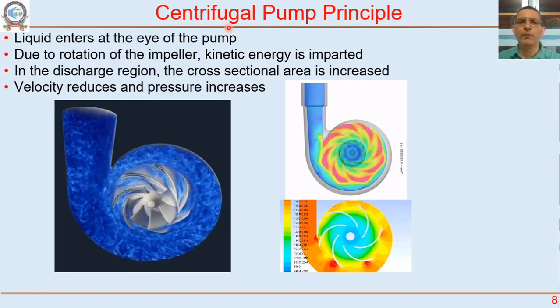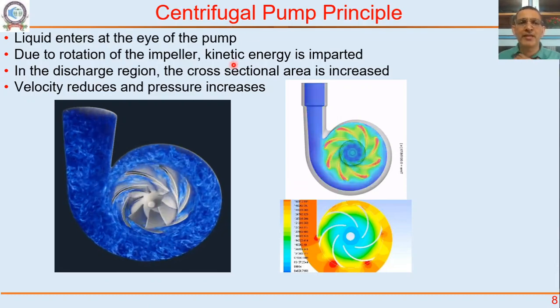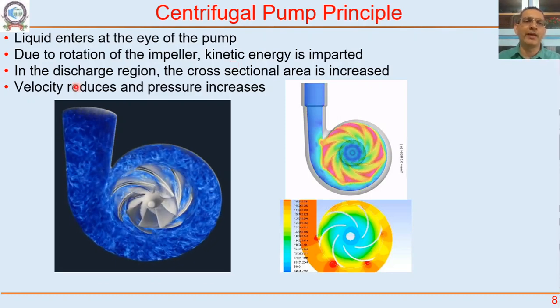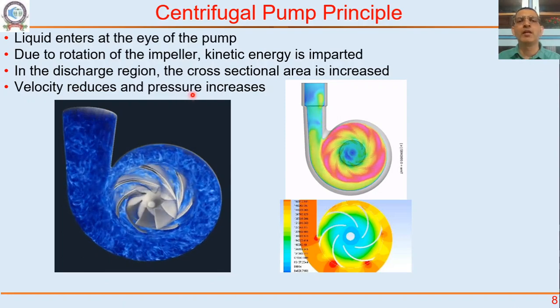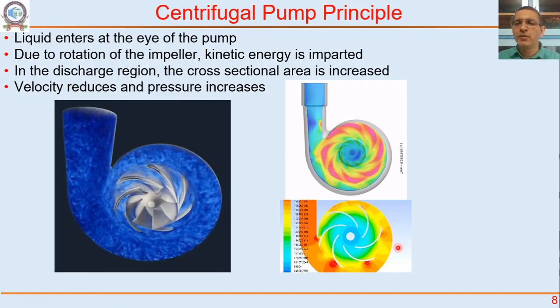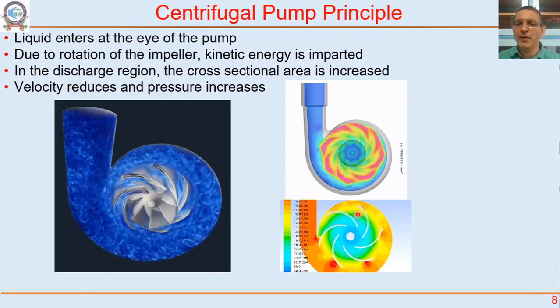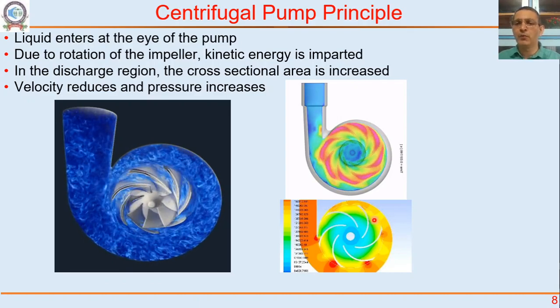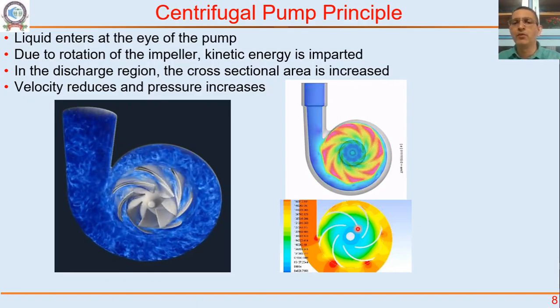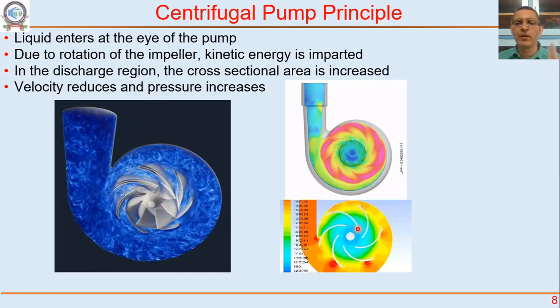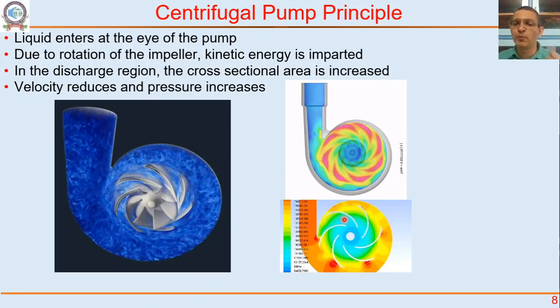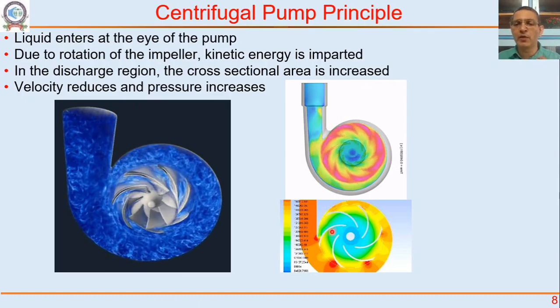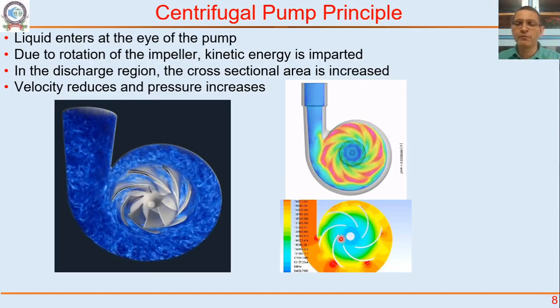So in a centrifugal pump, centrifugal action increases kinetic energy, but later inside the pump the kinetic energy is reduced and correspondingly pressure is increased. You can see the low pressure regions where liquid can vaporize — that is where cavitation can happen. We talked about net positive suction head: liquid goes inside, it cavitates, vapors are formed, and the pump is not able to handle vapor. Those things will become clearer now.